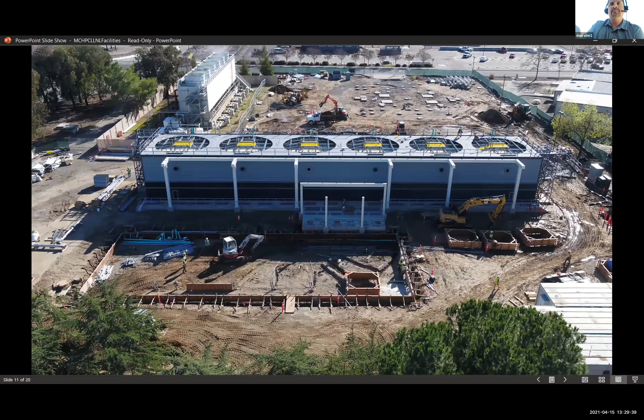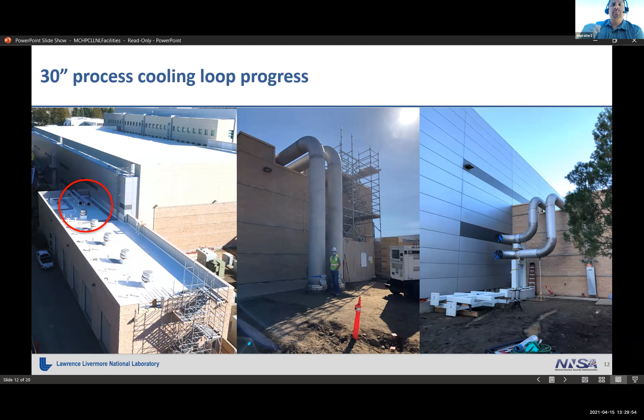Here's a little close-up of the new construction of our cooling towers. There's our 30-inch pipes going up above our chiller room, and up over, we have 3 taps that will actually penetrate the building and have a capacity of 10,000 GPM per tap.